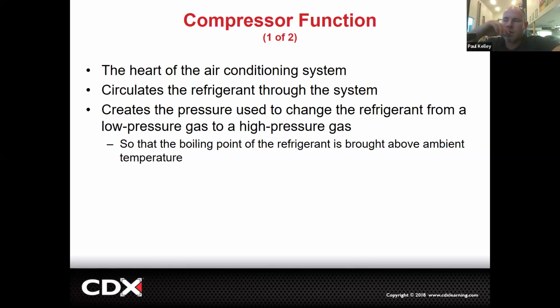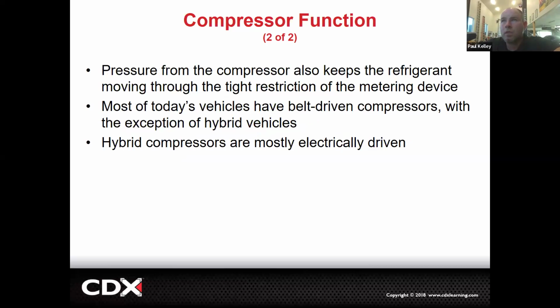So if we need to make the condensation occur at 200 psi, that compressor needs to be able to make 200 psi. If we need 30 psi to make that evaporation occur in the evaporator, that compressor needs to be able to pull down to 30 psi. It has to. If the compressor can't keep up, you're not going to get the change of states. You're not going to have the correct pressures, and therefore you're not going to have cold AC. It's just not going to happen, right? And these compressors, they're kind of a wear item, right?